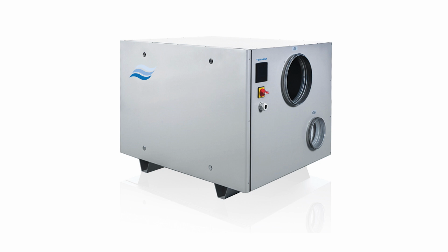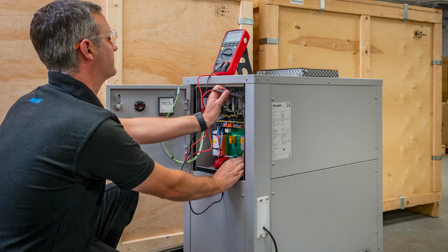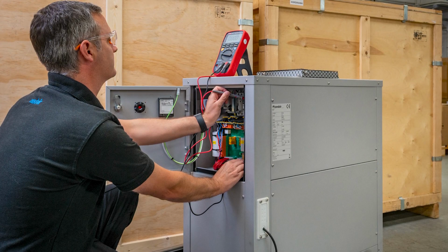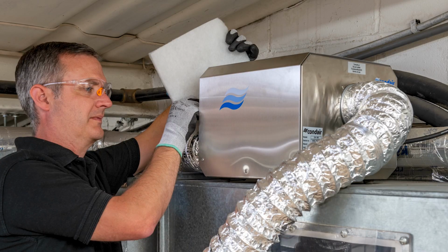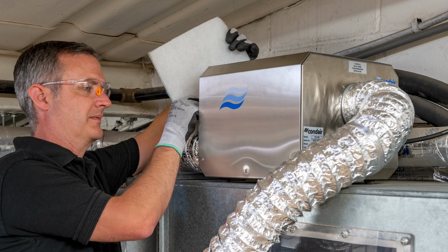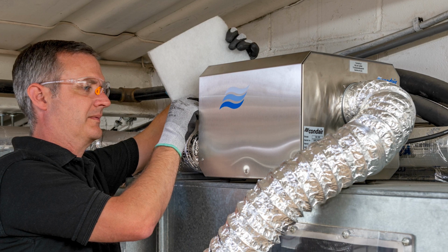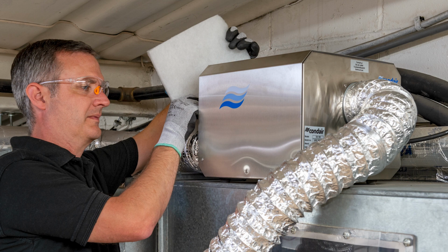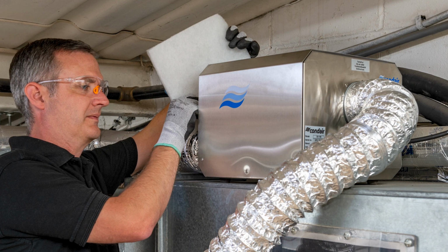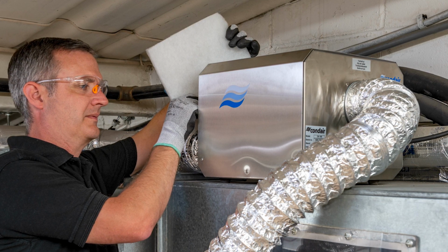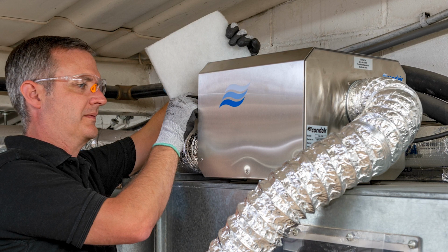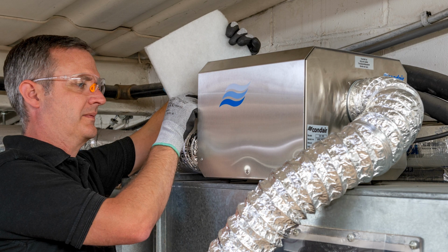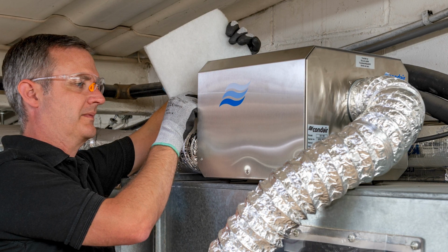Well, the other main thing to mention is the simplicity of installation. Our condensing system is the easier of the two to put in. All it needs is a power supply and a drain. Whereas the desiccant unit will always need a duct to vent the wet regeneration airflow. Now, there's no liquid moisture within the desiccant system, so you don't need a drain. But the hot, wet exhaust air needs to be ducted outside. Now, depending on the location in the building, this can sometimes prove challenging. Okay, so I think we've got a handle on the elements affecting unit selection.